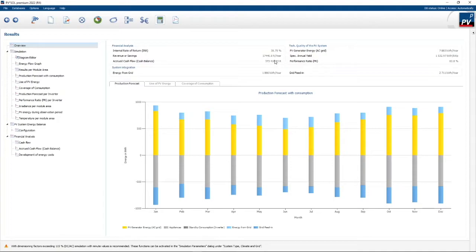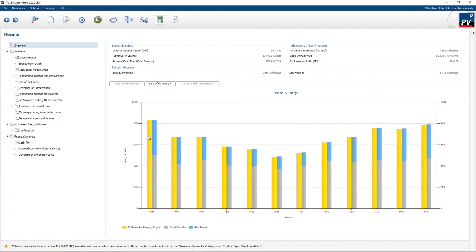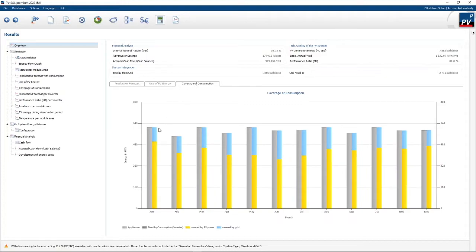Not bad on an investment of 50,000 rand. On the AC side, 7,800 kilowatt hours per year are generated with a specific annual yield of 1,022 kWh per kilowatt peak. There are also some interesting graphs — the use of PV energy graph shows the orange part as PV generated, the gray part as how much you use, and the blue part as how much you feed back into the grid, per month. The coverage of consumption graph shows how much is covered by PV versus the grid.